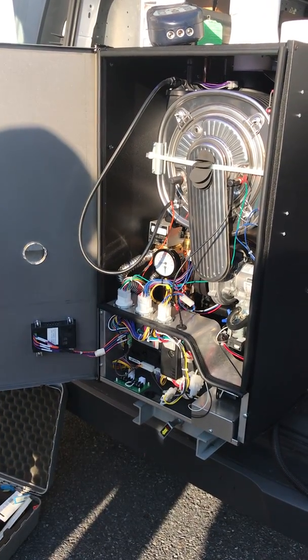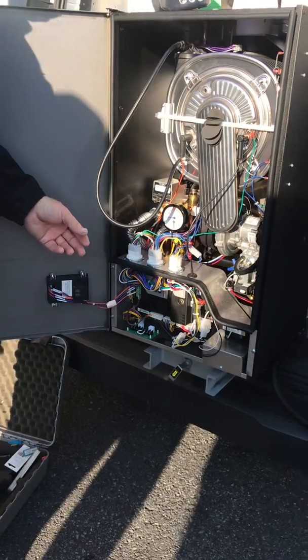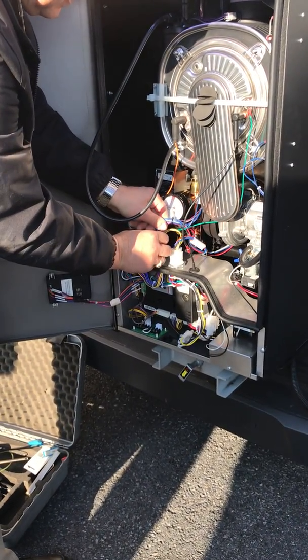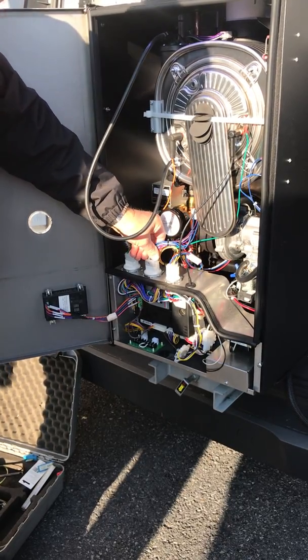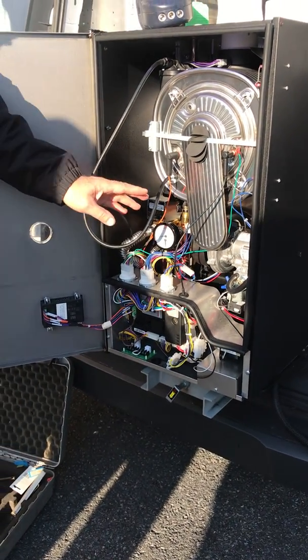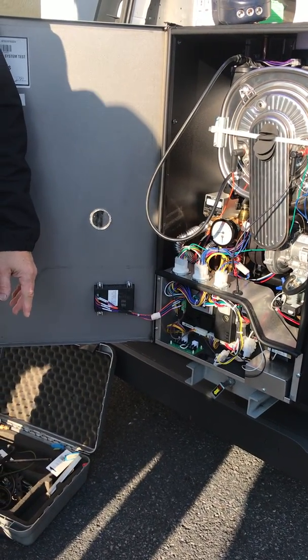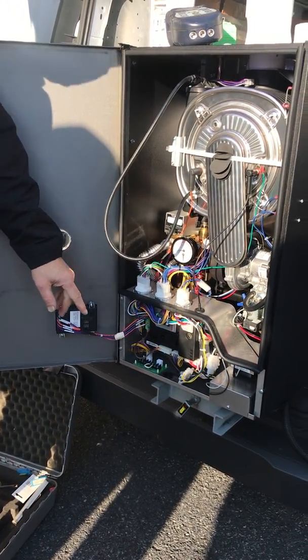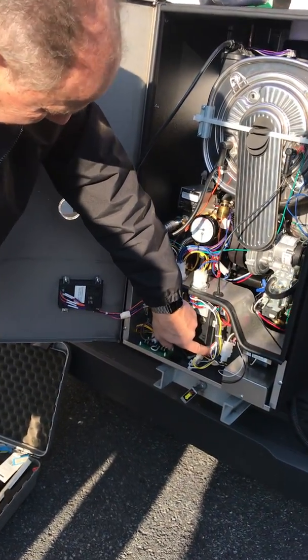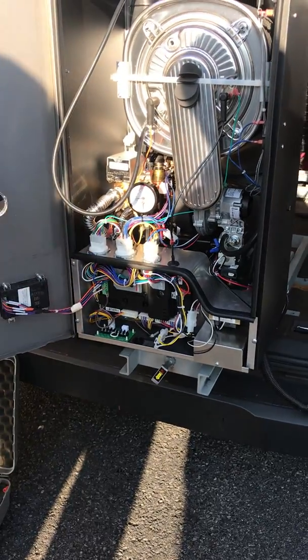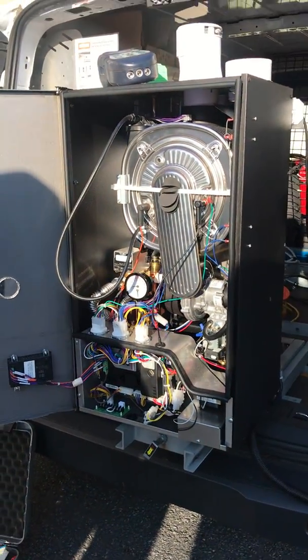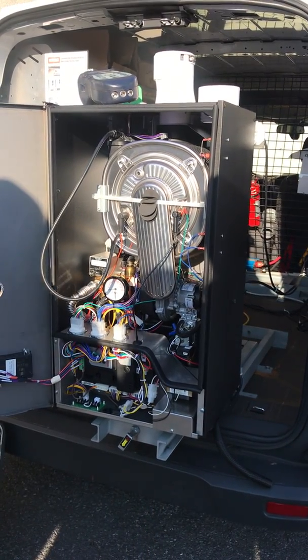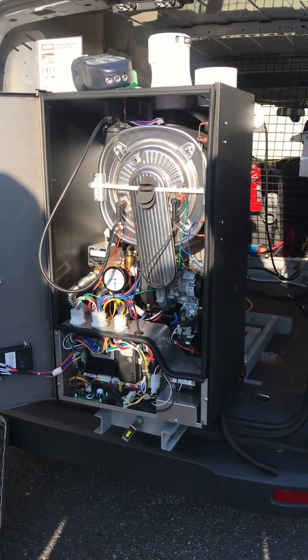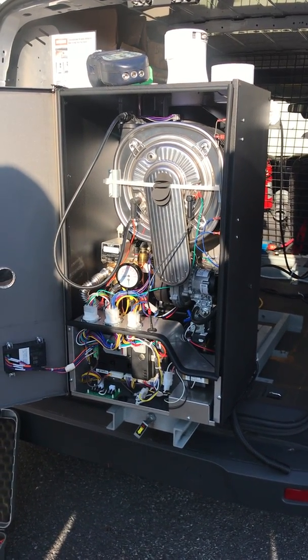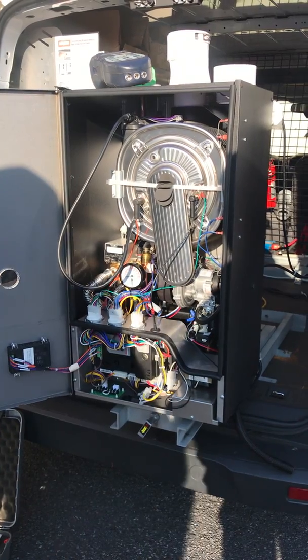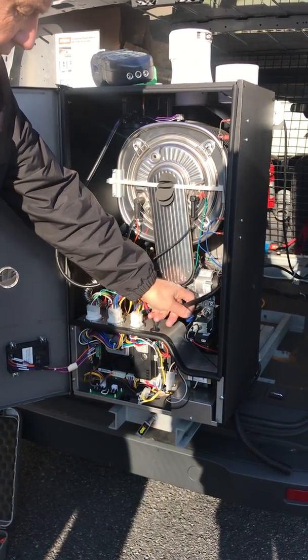If you're ever at a job and you want to know whether your blower's working or not, nothing's happening and my blower doesn't start, I can actually disconnect these wires. And there's 2 sets of wires that go to the blower. There's a power wire, a black, a white, and a green. And then there's a 4-wire signal, which is a white, a blue, a gray, and a red. So those 4 wires go to the blower and give it a signal. So if I undo the signal, the blower should run full speed. If it doesn't kick on full speed, I got a dead blower. So I'm just telling you real quick, you can actually, and everybody's equipment's the same way. We're gonna go through on the gas valve, there's 2 adjustments.